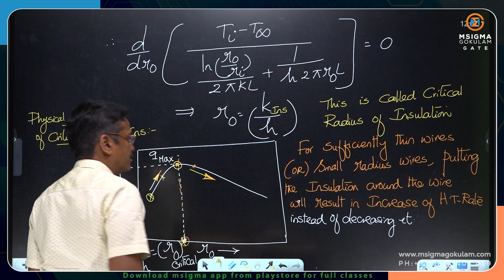I said sufficiently thin wires. Why I am using this word is, we are beginning the journey by considering a wire whose radius is the critical radius. If we calculate for practical values of the insulations and practical values of h, this r_o will be quite small, maybe 1 centimeter or 1.5 centimeter. That means you have to take a wire whose radius is 5 mm or 6 mm or 7 mm like that. So the critical radius concept is more applicable for sufficiently thin wires or small radius wires.